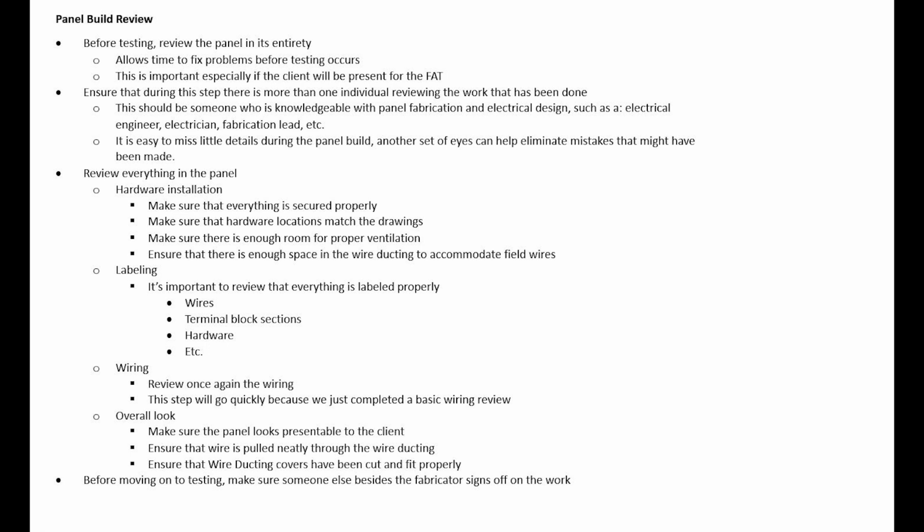The next thing we want to do during this review process is make sure that we actually review everything in the panel, everything that was involved in that fabrication process. So this includes things like all of the hardware installation. We're going to go through all of our terminal blocks, power supplies, and circuit breakers, and make sure everything is secured properly. We want to make sure that all the hardware is in the proper location, and that it matches the drawings and the layout that we are going to be providing.